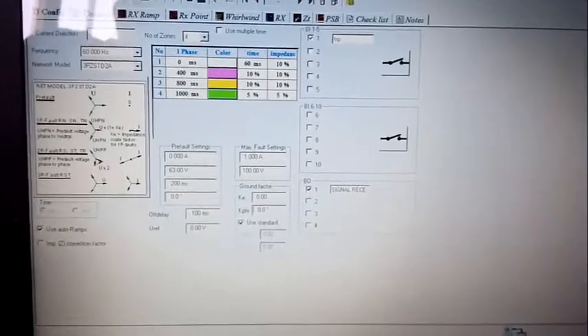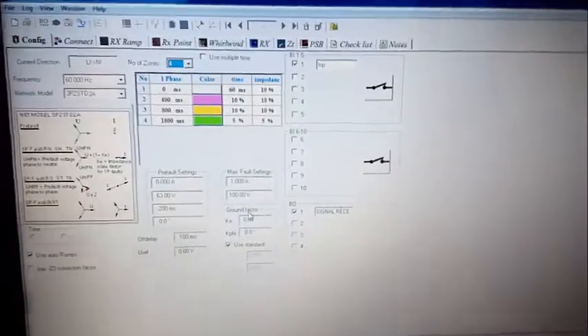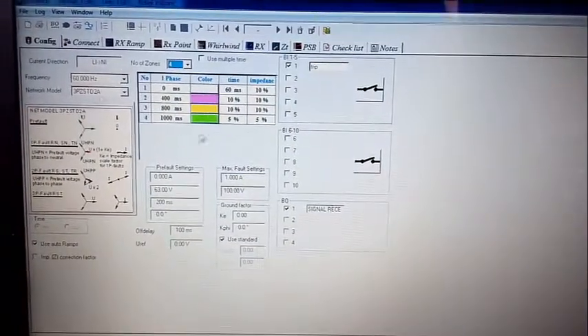Now we go to FREJA. When you connect your PC to FREJA, go to Configuration and enable the number of zones. We will do this for four zones, so enable four zones. Disable the ground factor — this will be used when checking phase with neutral. Set it to zero. Configure the binary output and binary input as needed. After finishing this, we will draw the zone lines.